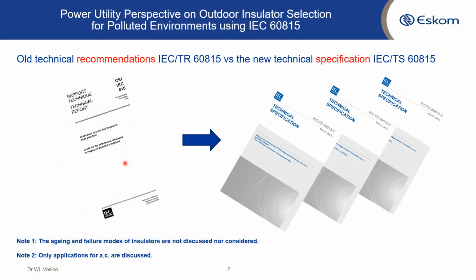The old technical recommendation served us as utilities well. However, with new technologies becoming available, hydrophobicity transfer materials, RTV coatings, new profiles, new manufacturing techniques, and so on, and also with the methodology of doing site pollution severities, a lot of work has been done in CIGRE and by IEC to end up with these four documents, which is the new 60815.